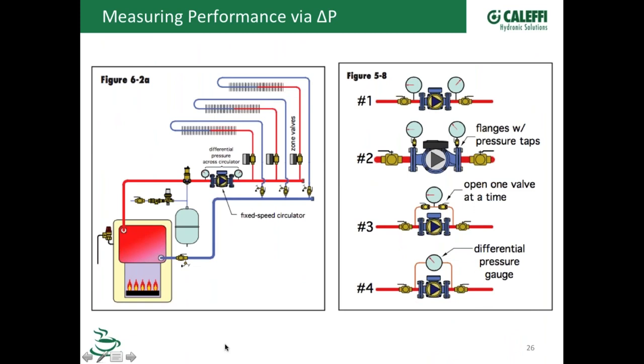The other thing I want to show you here is, let's say you've got a job and you're not sure that circulator was sized right. Maybe the person before you, whoever installed that, didn't pay attention to the sizing. How do I know what the circulator is doing? How do I know if it's the right one or not? We go over an example of this in Hydronic 16, but if you have a way to put a pressure gauge on both sides of the pump when it's running, you'll measure, like you can see in the little needles here, the pressure differential that pump is establishing when it's running.